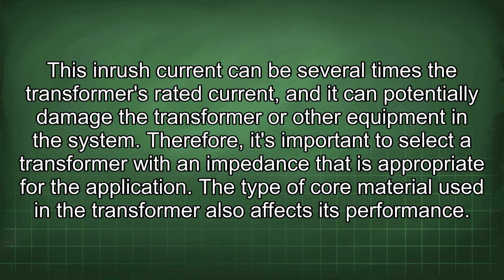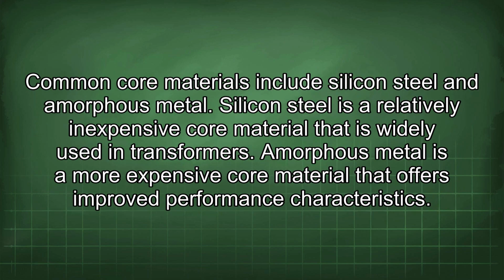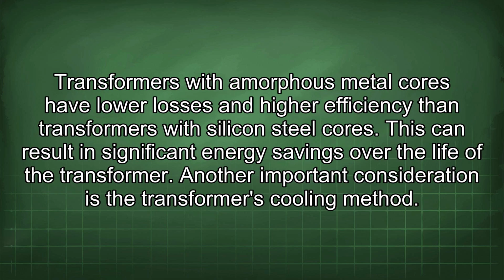The type of core material used in the transformer also affects its performance. Common core materials include silicon steel and amorphous metal. Silicon steel is a relatively inexpensive core material that is widely used in transformers. Amorphous metal is a more expensive core material that offers improved performance characteristics. Transformers with amorphous metal cores have lower losses and higher efficiency than transformers with silicon steel cores. This can result in significant energy savings over the life of the transformer.